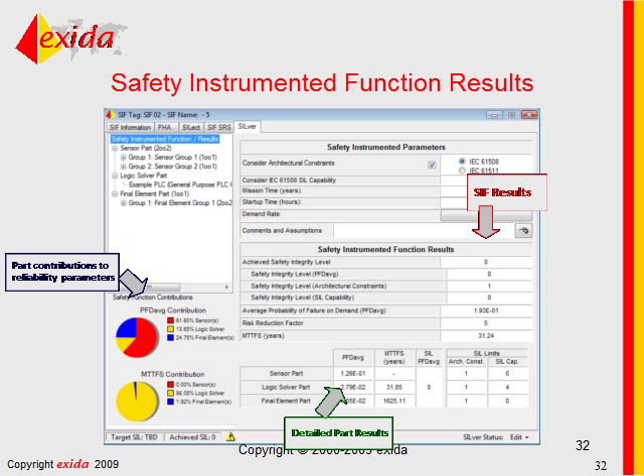But if you pipe up 2 of those valve assemblies such that you only need 1 to do the safety function, that's called 1 out of 2. So you could either call that one group with 2 valves with internal voting of 1 out of 2, or you could define that as 2 groups. Each group is 1 out of 1, and the voting between groups is 1 out of 2.